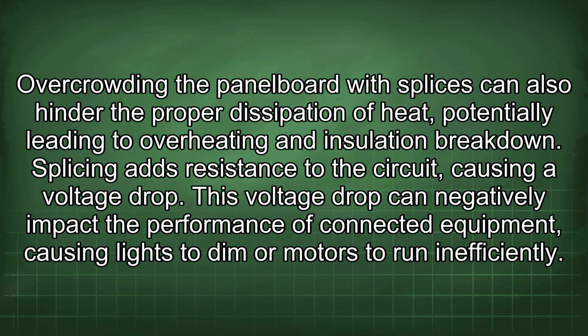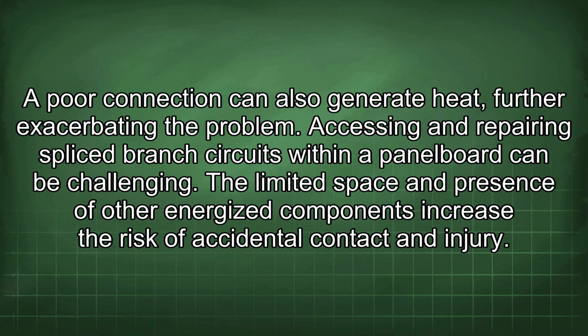Splicing adds resistance to the circuit, causing a voltage drop. This voltage drop can negatively impact the performance of connected equipment, causing lights to dim or motors to run inefficiently. A poor connection can also generate heat, further exacerbating the problem.